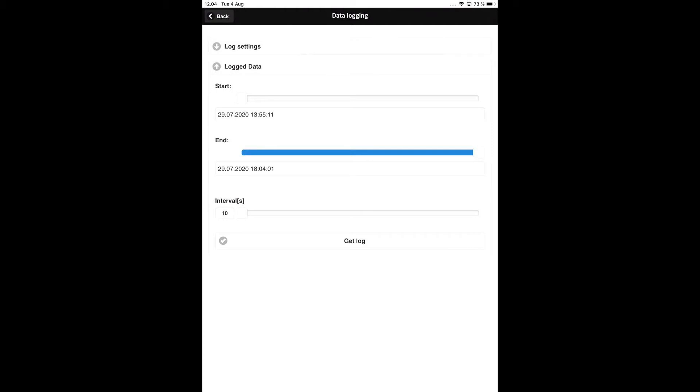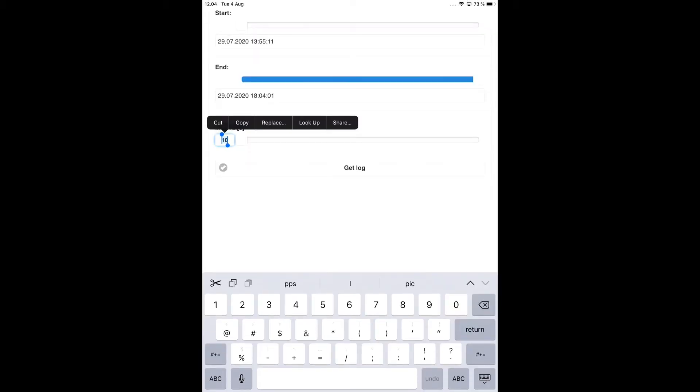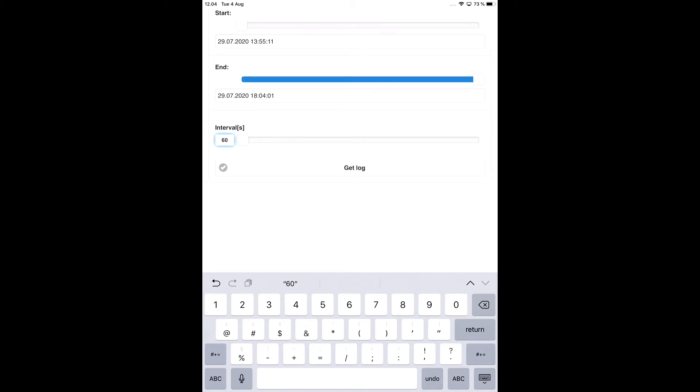Another way to reduce the size of the data log is to increase the upload interval. Here, I am choosing an upload interval of 60 seconds. Since I configured the 4512 to record a log every 10 seconds, only one sixth of the logs saved in 4512 memory will be uploaded to PPS, reducing the upload time.